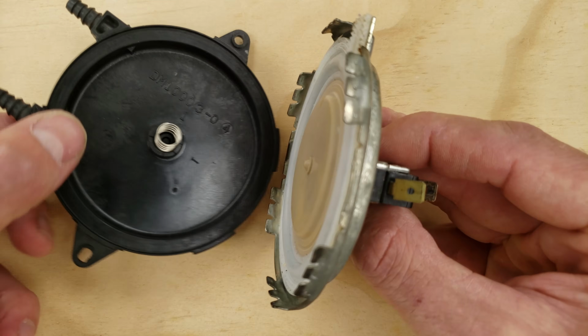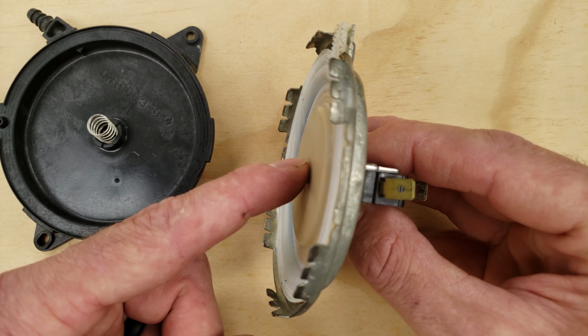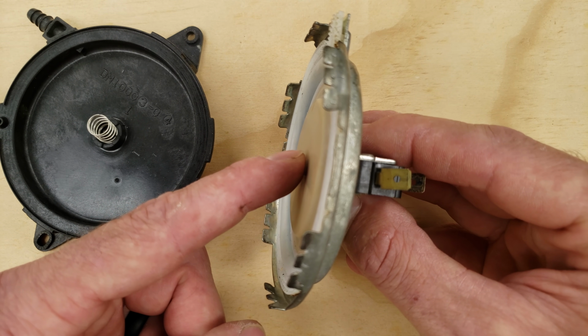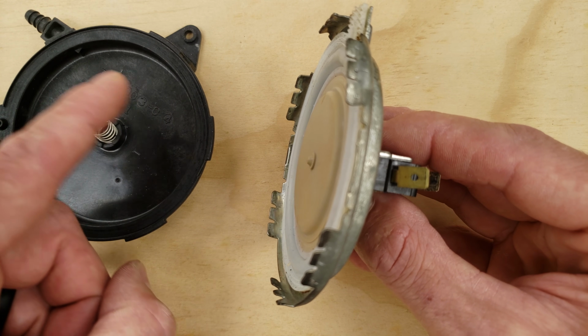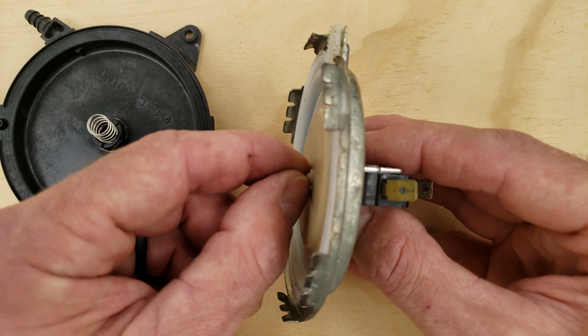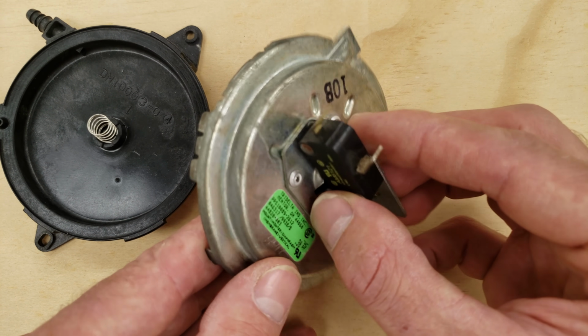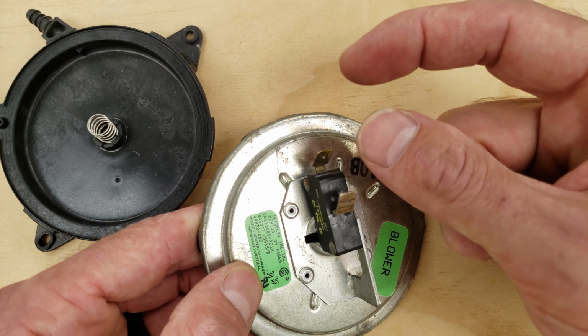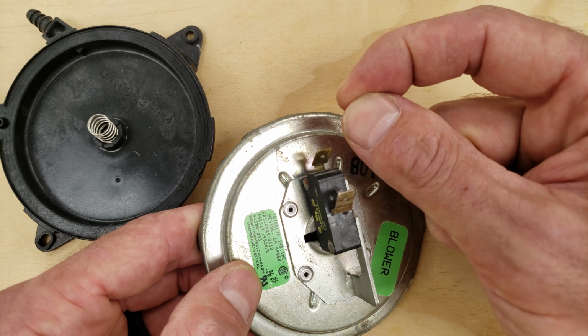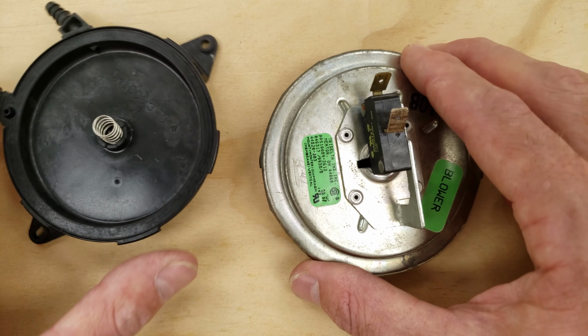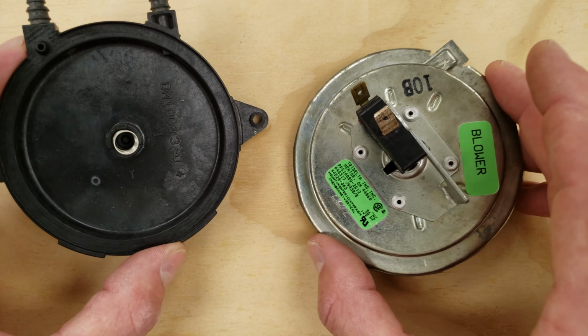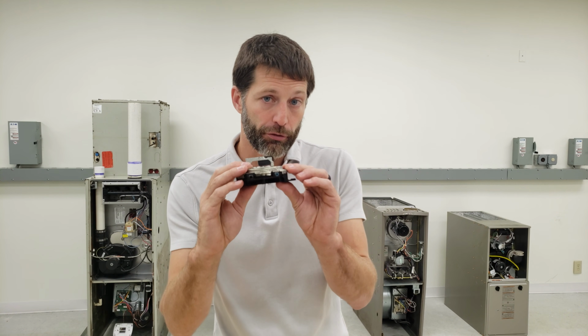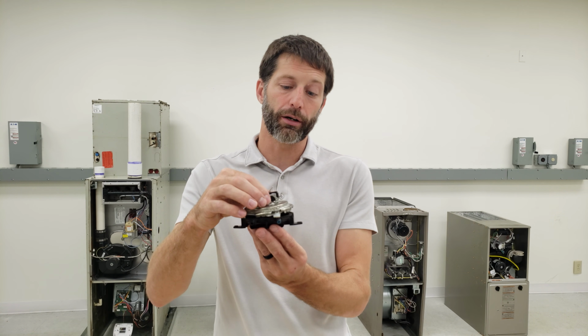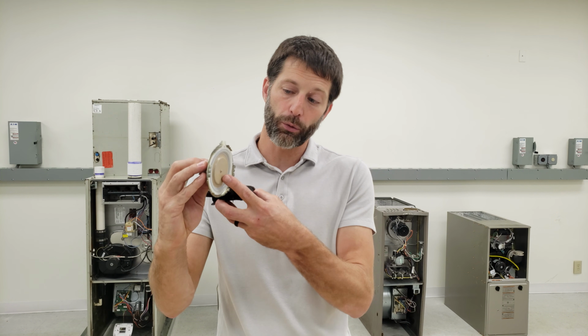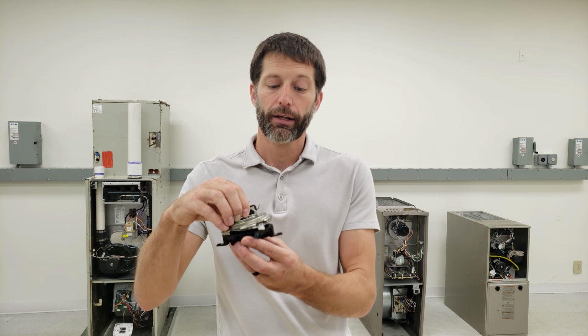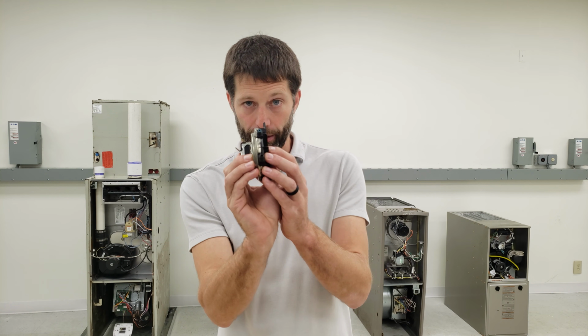So we're normally pressing like this on the diaphragm, and what's going to happen is the pressure in this chamber is going to reduce, and it's going to allow the diaphragm to come this way, and the normally open set of contacts are going to close during operation as long as the inducer motor is running and there is that pressure differential. You want to remember that a pressure switch is not mounted in a gas furnace like this, because then this spring would have to deal with the weight of the diaphragm sitting down on it. It's always mounted just like this.